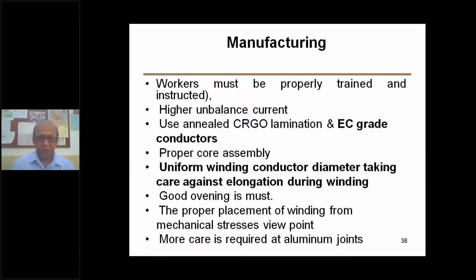Then proper placement of winding from the mechanical stress point of view. Yes, a symmetrical placement is needed for both LT and HT winding, right? Placement must be symmetrical, this must be seen. If placement is not symmetrical, then you are unnecessarily inviting axial forces to damage the transformer.